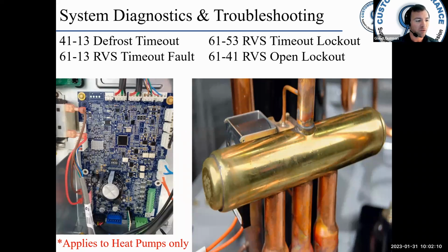The reversing valve only actuates when the pressure difference between the suction and discharge of the compressor is above a minimum level. Okay, so 6113 is set whenever the minimum pressure condition prevents a reversing valve from switching for 10 minutes. 6153 is set when 6113 has been declared 4 times in 2 hours. The 6153 results in a 2-hour lockout.